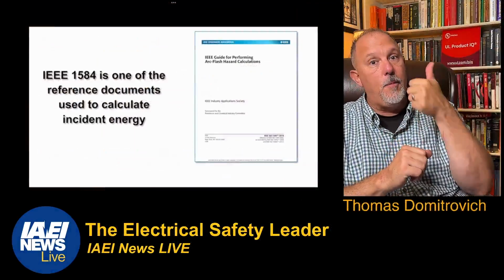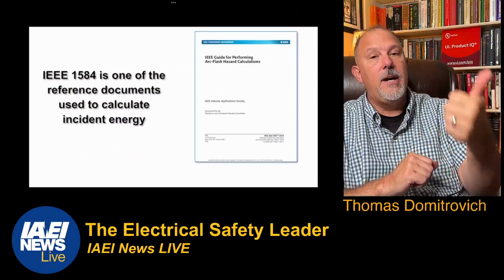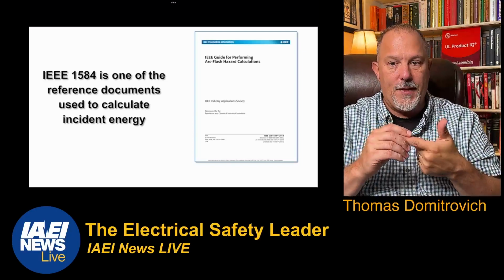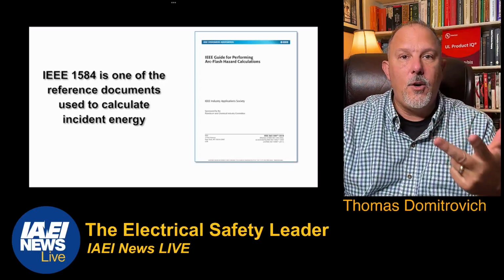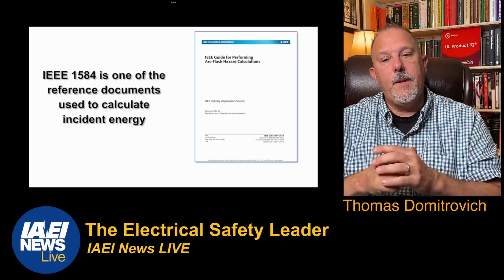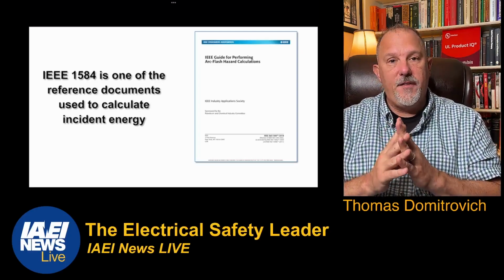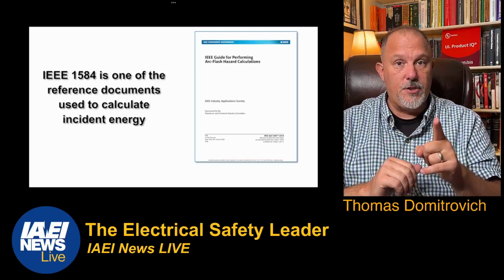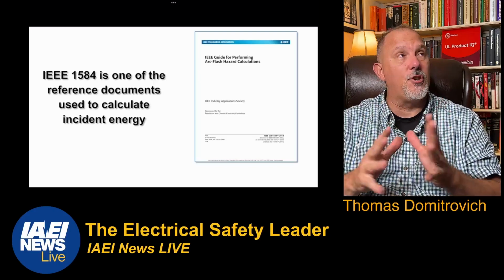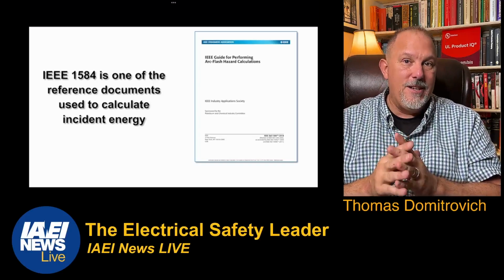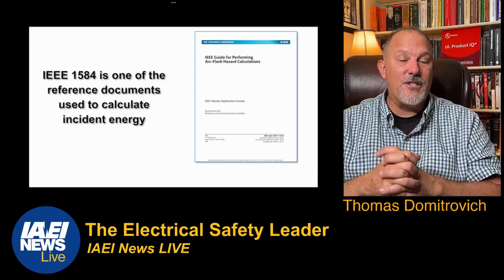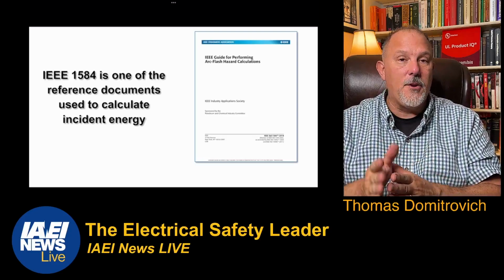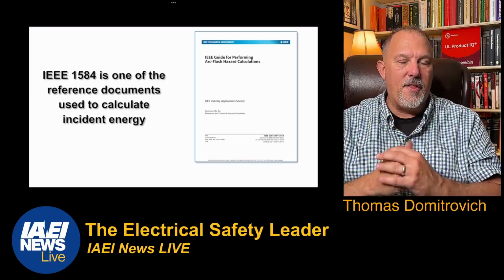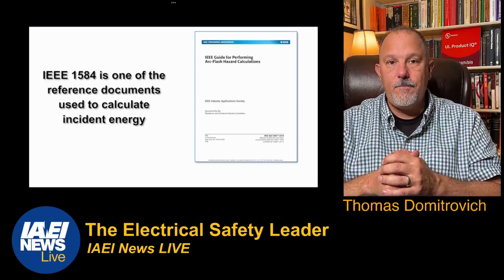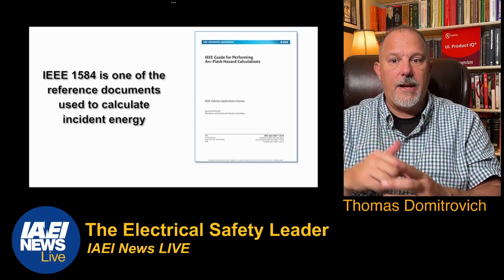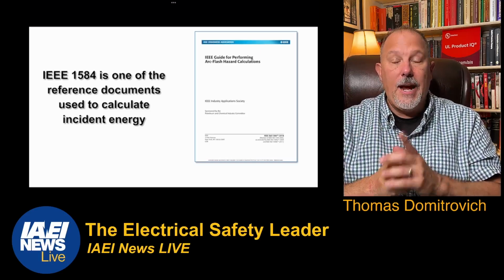So remember the parameters. First, I need to know bolted fault current. We have equations for that. I need to know the arcing current. We need equations for that. Hint, hint, hint. And we need to know arc flash. So in 2002, IEEE 1584 was first released. Think about other things that were going on in the National Electrical Code. In 2002, that was when we introduced Section 110.16 for arc flash labeling in the NEC. That's the same year that 110.16 was introduced, and we ended up with a, hey, this could be a hazard type of label. Today, 110.16(B) closely reflects the work of IEEE 1584 committees and the testing that was done.